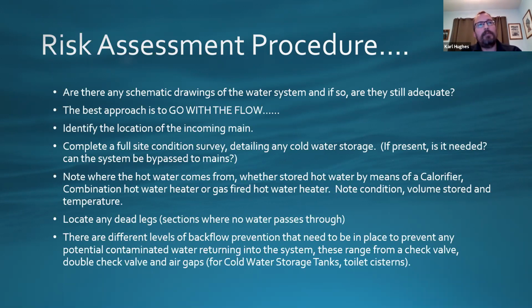Note any cold water storage tanks, any hot water storage, whether it's calorifiers and things like that, what their conditions are, and whether the temperatures are compliant - whether the cold water is less than 20 degrees and the hot water is greater than 50 degrees at the outlets.